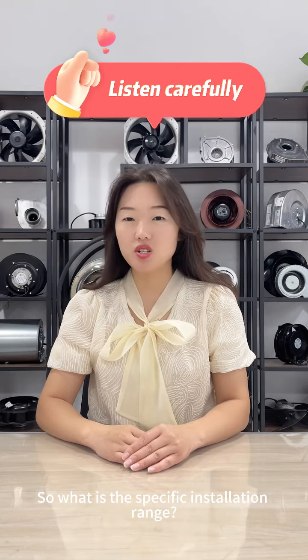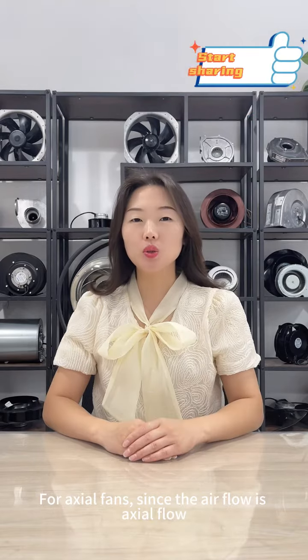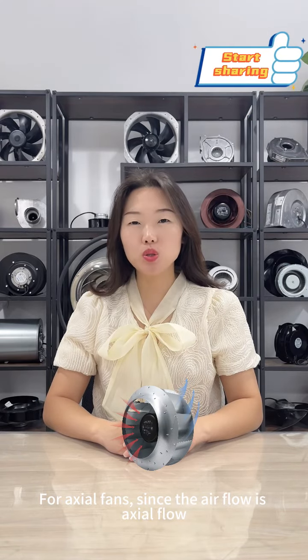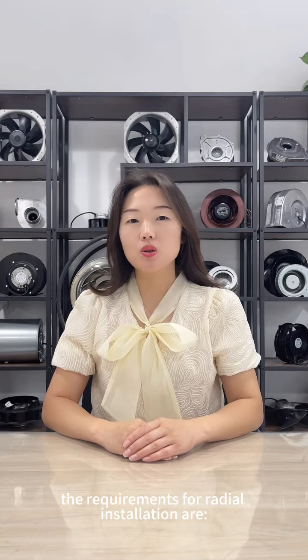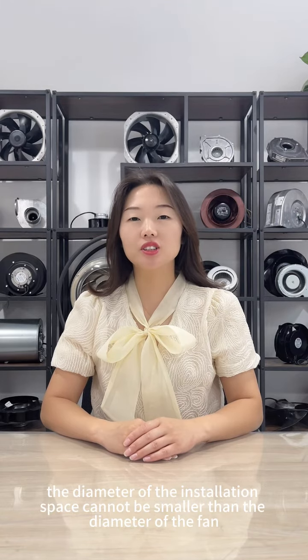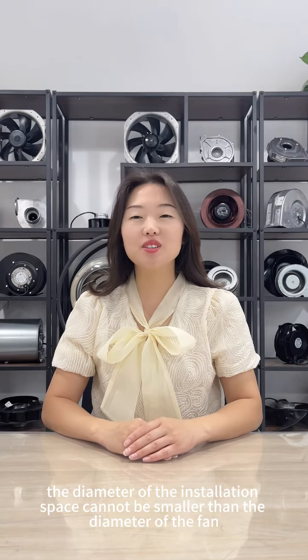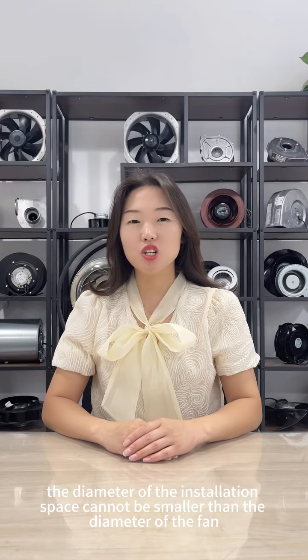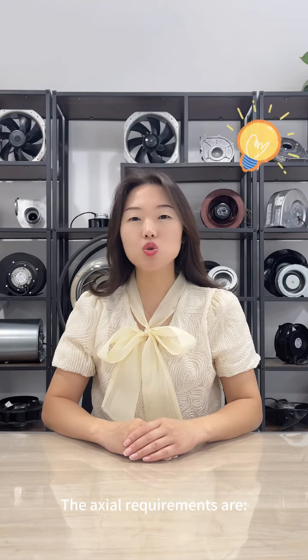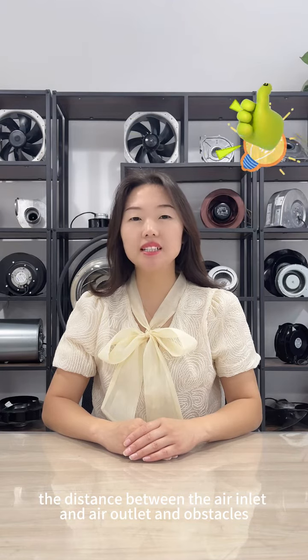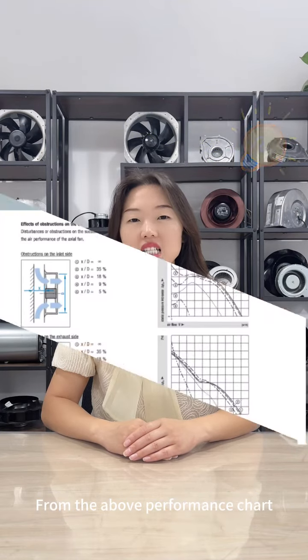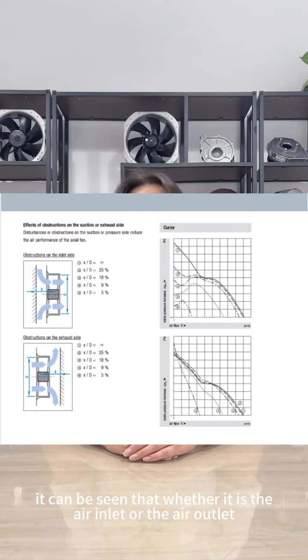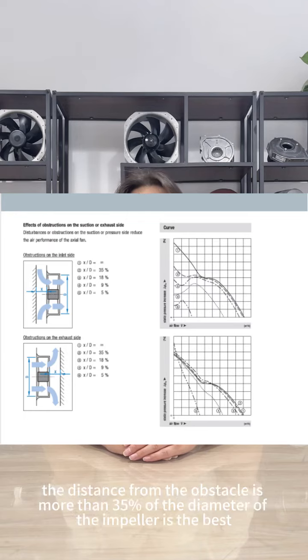So what is the specific installation range for axial fans, since the airflow is axial flow? Therefore, the requirements for radial installation are: the diameter of the installation space cannot be smaller than the diameter of the fan. The axial requirements are: the distance between the air inlet and air outlet and obstacles. From the above performance chart, it can be seen that whether it is the air inlet or the air outlet, the distance from the obstacle is more than 35% of the diameter of the impeller is the best.